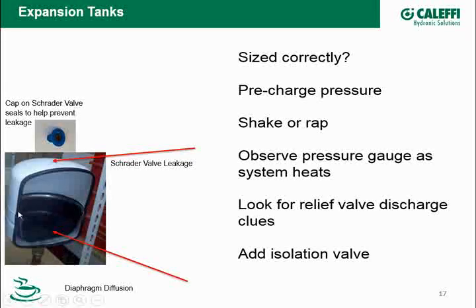And he went over quite a bit of this. I mean, there's what we call an acceptance in the tank volume, and the reason for that is you can't stretch this diaphragm completely to one end. So even though this tank might hold 4 gallons of fluid, it might say it's a 4-gallon expansion tank, the acceptance of that might only be 2 or 2.3 gallons because you can't stretch that in there. So I thought having a little cutaway kind of shows you a little better what's going on inside that tank.